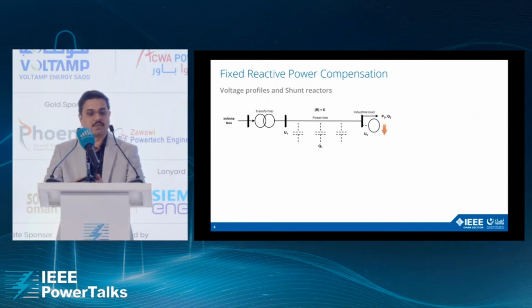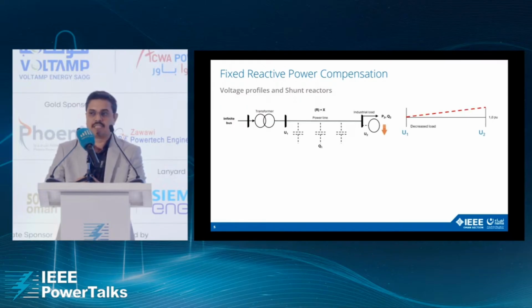But imagine a situation when the demand from the industrial customers drops down. In such a scenario, you will have more reactive power generated in the system than is consumed by the customers. In that condition, due to the Ferranti effect, we will have a very high increase in the voltage at the receiving end. And this can put the insulation under stress. Much equipment can get damaged, which we don't want.